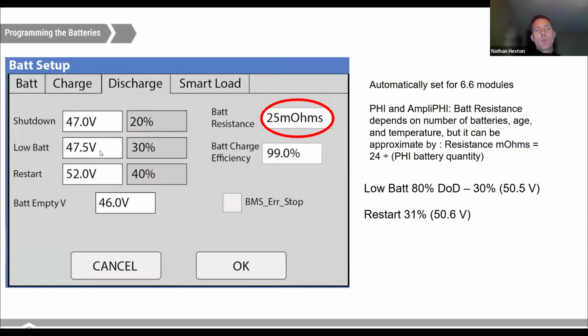Low battery is when the inverter will indicate to the homeowner that the battery is getting low. We typically recommend somewhere around 49.5 volts, which would be about 15% overall battery capacity, 20% battery capacity for low voltage if you're discharging all the way for an occasionally cycled battery. For a battery that is going to be cycled daily, we'd recommend these values at 30%, and then 50 volts here for low battery. That's when the inverter will just start giving you a beep indicating that the battery's getting low.